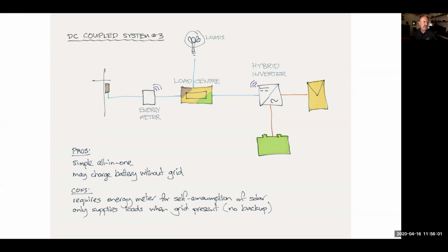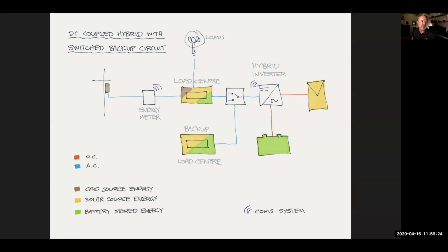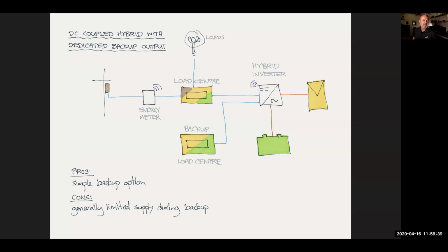So just to summarize, DC coupled systems are simple. They may charge batteries without the grid. They require an energy meter for self-consumption of solar where the load center is upstream of the hybrid inverter. And in this diagram, only the loads are supported when the grid is present, no backup. However, it is possible with some of those hybrid inverters using an automatic transfer switch to add a backup capability. And there are some which have a dedicated backup circuit output as well, such as this. So this would be where the hybrid inverter has 2 AC ports, one says grid, one says backup. And some of these switch very, very quickly too. It's still a break, but it's often 10 milliseconds or so. So if you're looking at a virtual no-break system, some will do this. It's a very quick switch.